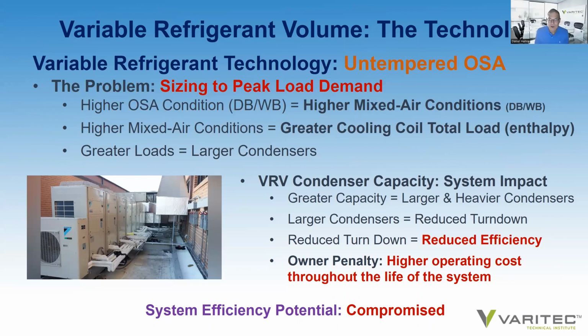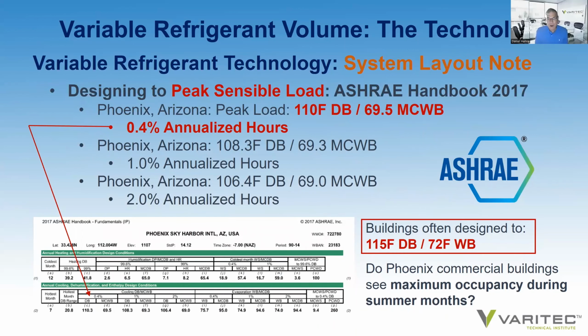So if you have VRV condenser capacities increased, what do you see? Larger and heavier condensers. Condensers that offer less turn down when variable refrigerant systems are most efficient, which is at part load conditions. You have larger condensers, you have greater first costs. And also the larger the condenser, the less turn down capacity you have, resulting in higher operating costs throughout the life of the system. So your system efficiency inherent in variable refrigerant technology is compromised. Just something as an aside to be aware of.